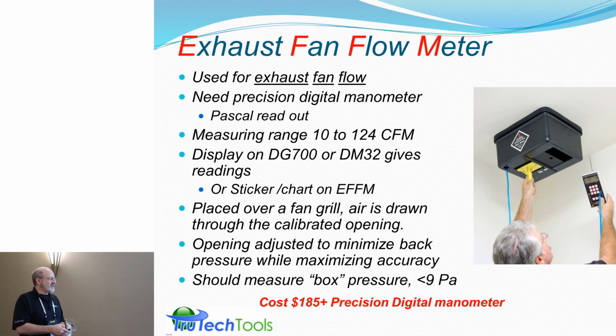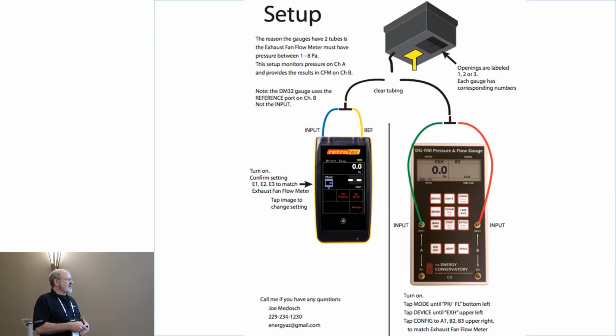The box is pretty cheap, but the manometer itself, you need to get a Pascal range manometer to do that. They're in the $500 to $1,000 range. There are actually some good instructions from a consultant, Joe Midash, who created this on how to hook up both of the meters. It's hard to see in this slide, but it'll tell you when you get above 8 Pascal, and it will also tell you the flow range from those 2 meters directly. So the setup steps are there.